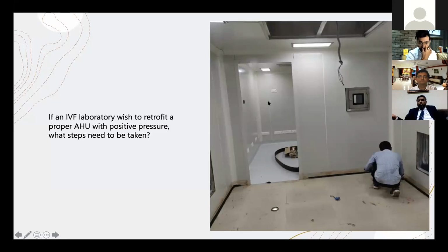I have to balance the airflow between the laminar flows. If you see a laminar flow happening from all four corners in two different chambers, balancing the airflow in all the corners requires a lot of high-technique, ISRO-type labs where we use some other fluid dynamic system to balance between the rooms. That's more expensive than just buying two different AHUs.